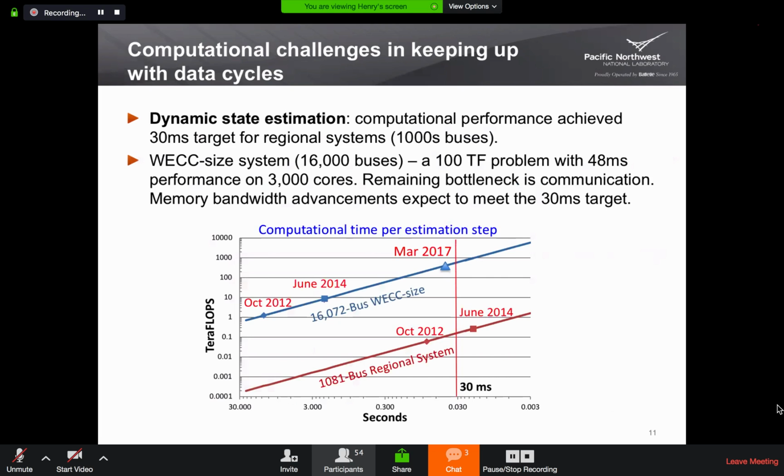So that's an application. But what I want to show today is just the challenge regarding speed. Think about state estimation. It's a real-time application. Your PMU data comes every 30 milliseconds. That means whatever mathematics or computation you need to do with the data, with the physical measurements, will have to be finished within 30 milliseconds. Anything slower than that, then you are falling behind. And that means you cannot finish computation before the next set of data comes in, and then that is not going to be useful, and you end up losing data or losing the view of the power grid.